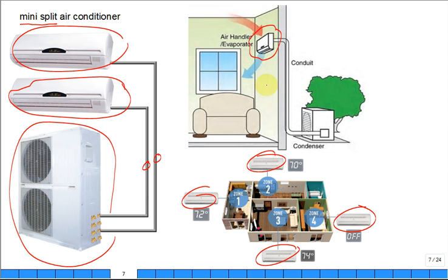A couple of advantages: no ducts in the attic. And if you have a duct in the attic, guess what the duct does? Leaks. All ducts leak. I've been in attics at Hobbs. The ducts are even just old and they fell off. And the thing is blasting cold air into the attic, and the people are complaining they have a $350 electric bill, and it's still uncomfortable inside the home. Check out your attic. Check out the ducts. Happens all the time, right?